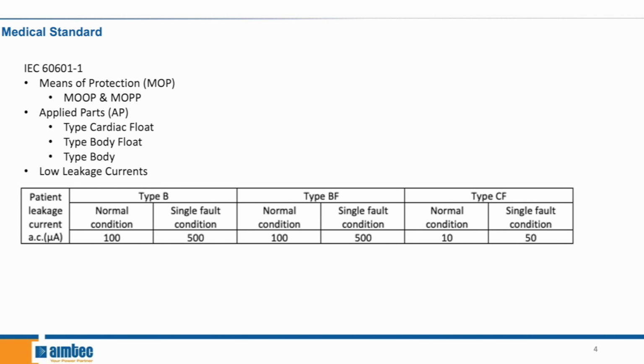So if we're looking at the table below, we see that for the least stringent type, body, or type B, we have 100 microamps under normal condition and 500 microamps under single fault condition. And if we look at the most stringent one, which is type CF, we have 10 under the normal condition and 50 under the single fault condition.